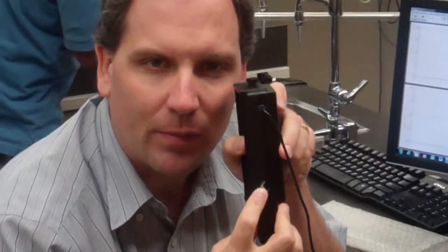So this has got two ranges. It's called a dual range force probe. Plus or minus 10 newtons, plus or minus 50 newtons. Most of the time, we will be working in the plus or minus 50 newton range, although sometimes we'll do it in plus or minus 10. So if you get one of these force probes and it says to use it in the plus or minus 10 newton range, you want to make sure that it doesn't have a sticker on here saying does not work in plus or minus 50 newton range or whatever. You see what I mean? Okay, so we're going to put it in the plus or minus 50 newton range. Now, one thing to be careful of is there's a little button on the side here. Don't hit the button. It'll screw things up.